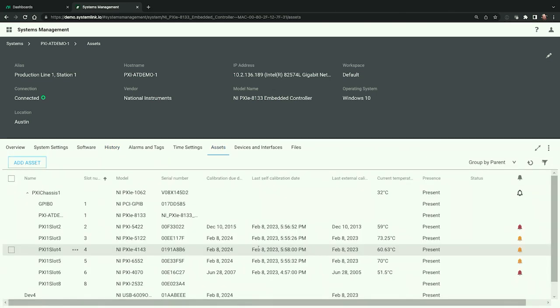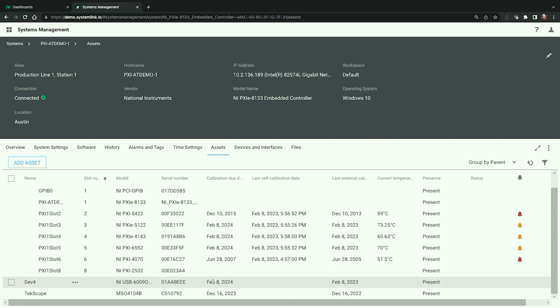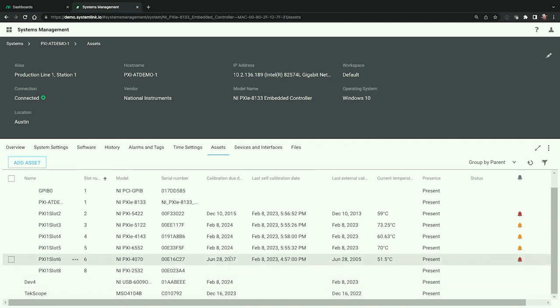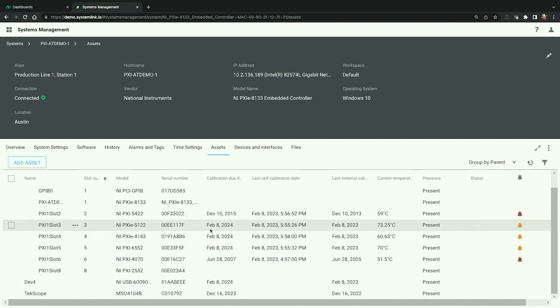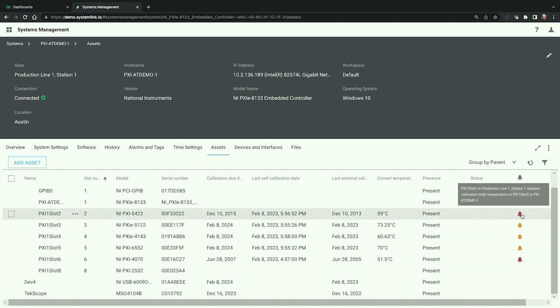If we switch over to the Asset tab, we can see all the equipment currently connected to this system — this includes NI equipment like our PXI chassis and modules, as well as third-party equipment like our Tektronix scope. In addition to seeing what instruments are connected, we can also see calibration information as well as sensor data like the current temperature of each module. SystemLink has built-in alarms and notifications so that as instruments near their calibration date, you'll automatically receive email notifications indicating which instruments need to be calibrated to ensure measurement accuracy.